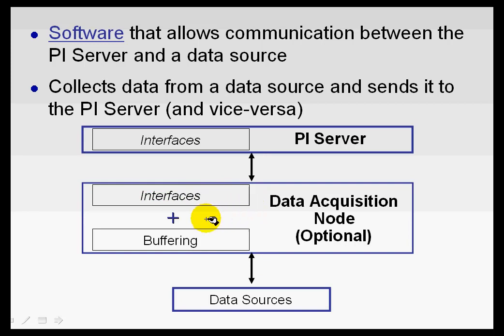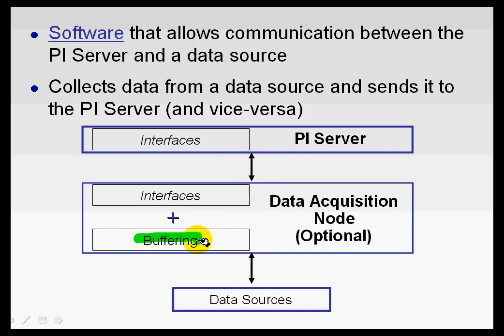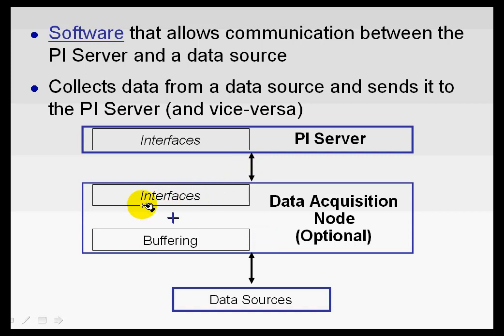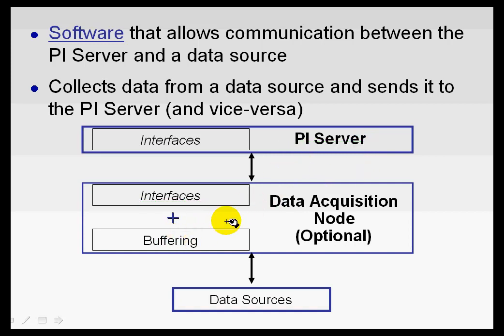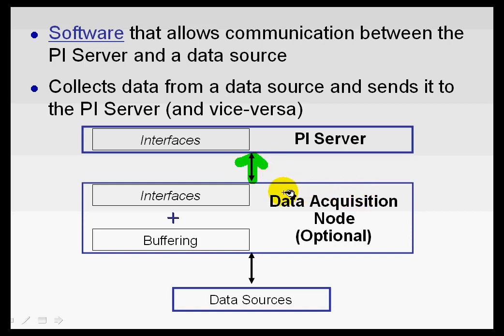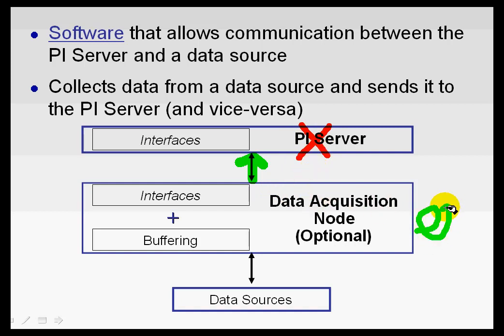Now, that interface generally is going to send the data directly to the PI Server, except we do have another layer called Buffering that is an option and a very highly recommended option. Buffering is something that will more or less get itself in between the interface and the PI Server. So, when the interface tries to send data to the PI Server, the buffering, which typically starts before the interface, is going to intercept it and then forward that along to the PI Server. Now, the beauty of that is if for any reason the PI Server is not available, then this interface will automatically do buffering using that buffering subsystem. So, we'll take that data and store it locally.